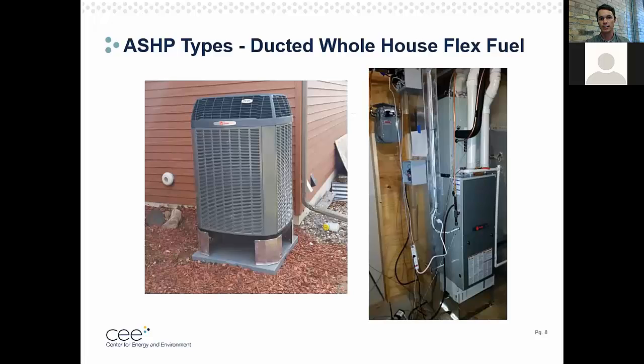But as you can see here, this outdoor unit on the left looks like your typical air conditioner. That is your outdoor air source heat pump with a ducted flex fuel system. So that's the outdoor unit. On the right is the indoor unit, and it's paired with a condensing propane furnace. So the unit connects to that indoor distribution or the air handler by putting the A coil through that system. And with it being propane, the propane can serve as the backup. And we'll talk about how that backup propane furnace that you see on the right interacts with the heat pump in the outdoor unit that you see on the left.